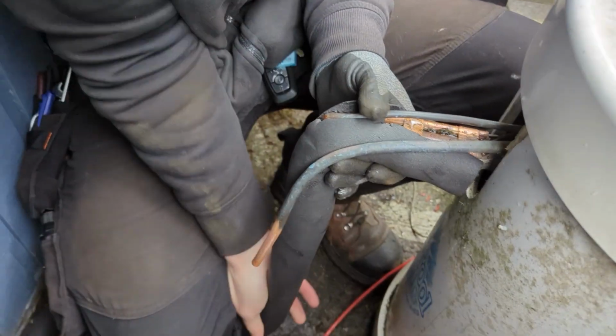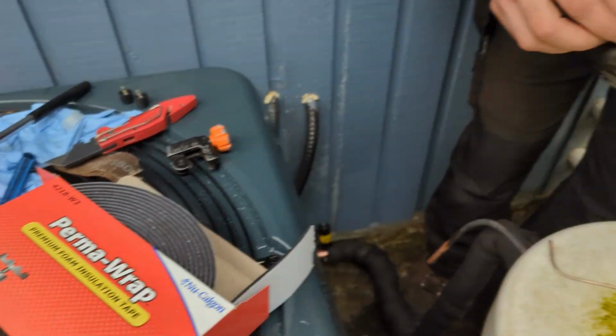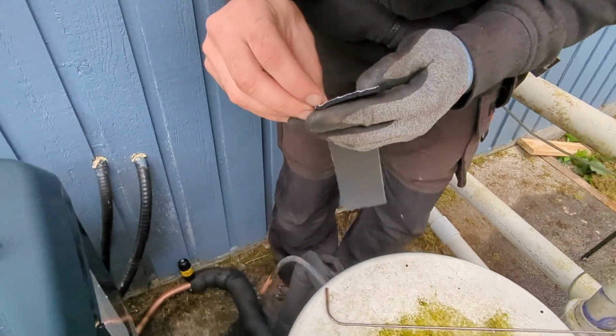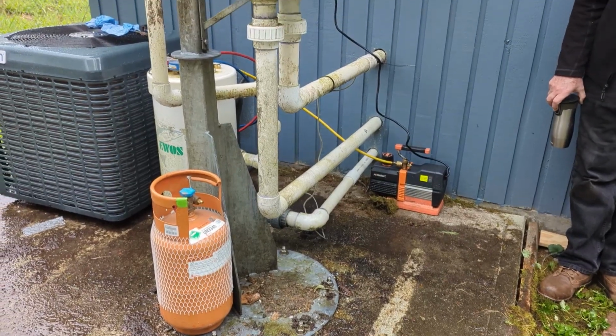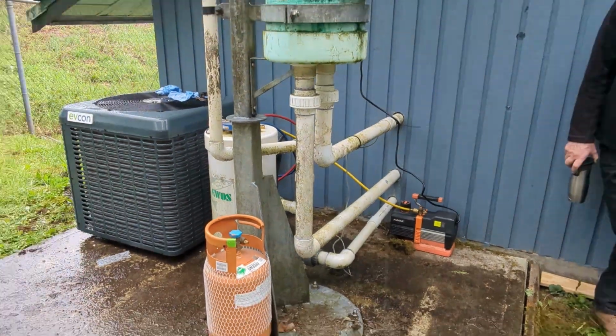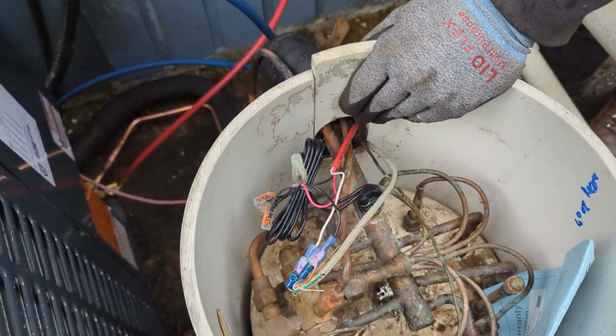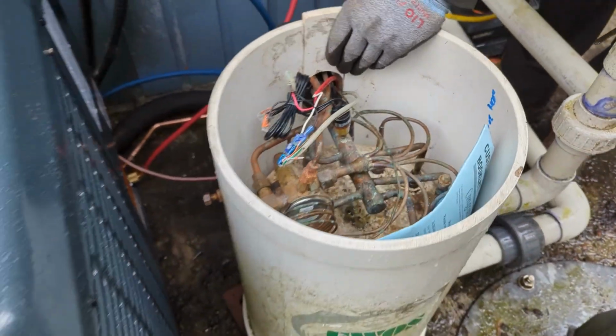Got some new Armaflex insulation for the suction line. I'm going to use some new Calgon Perma-Wrap tape to put that on properly. Now our system's on vacuum, and it went really quickly because our line set is so short. We've got all the pieces back together.